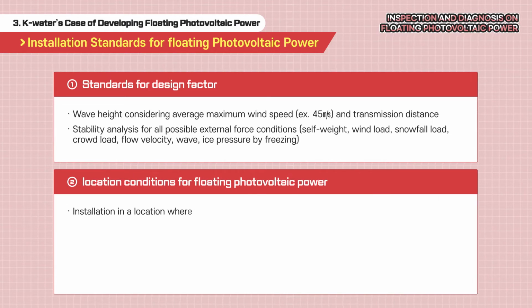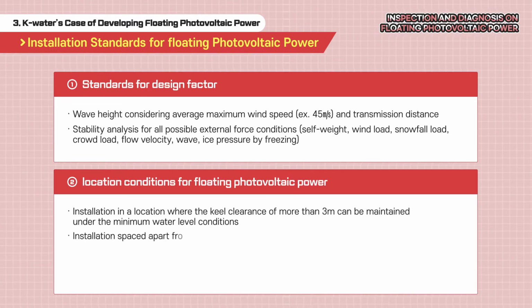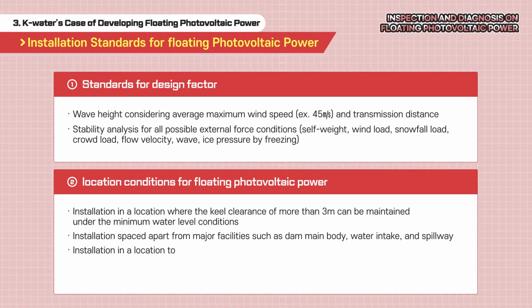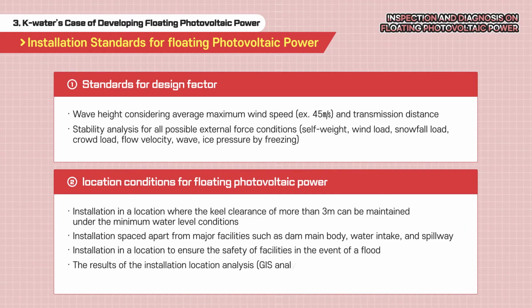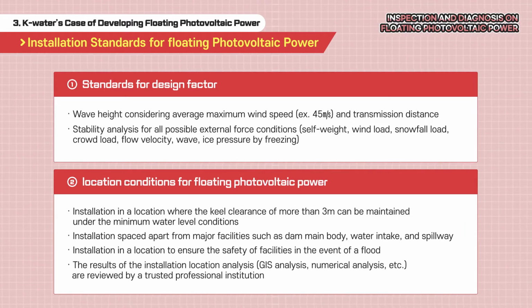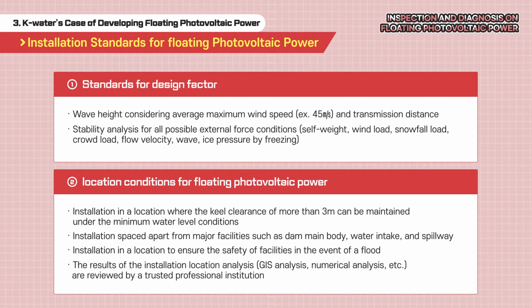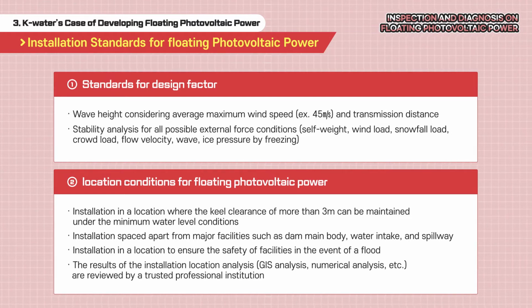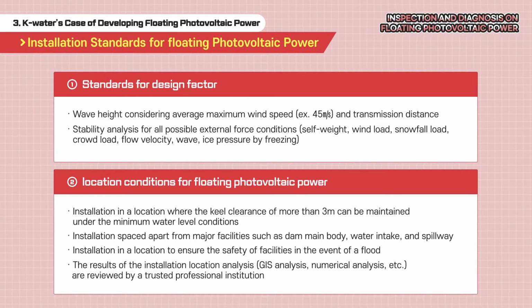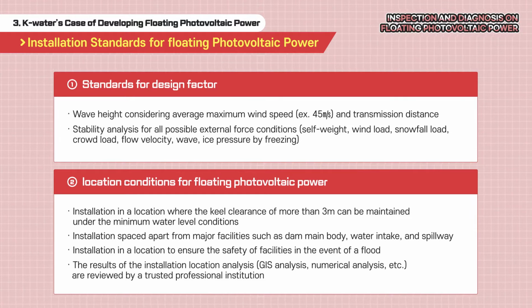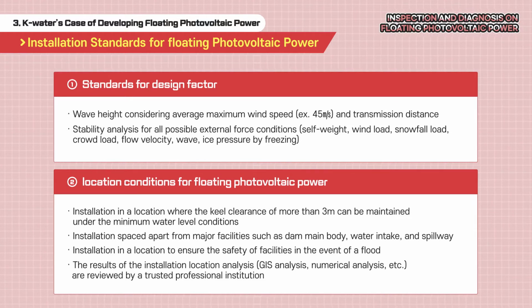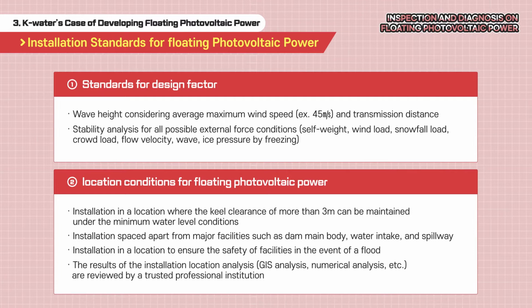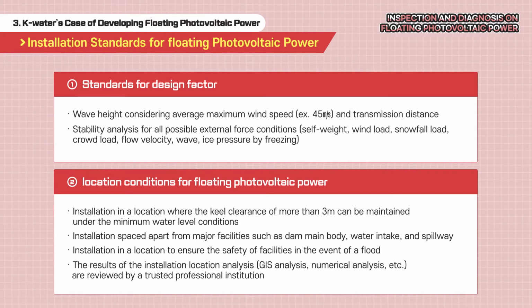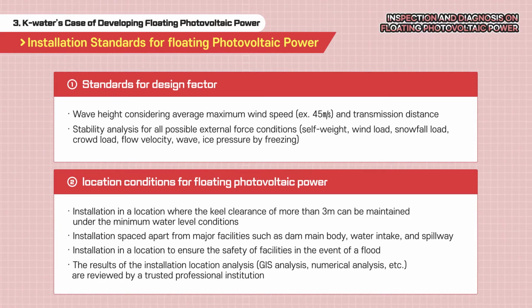Location conditions for a floating photovoltaic power system should be installed at a location that can maintain a keel clearance of 3 meters or more under the lowest water level conditions, maintain sufficient separation from major facilities such as dam bodies, water intake, and spillway, and pick a location where the safety of facilities can be ensured in the event of a flood.